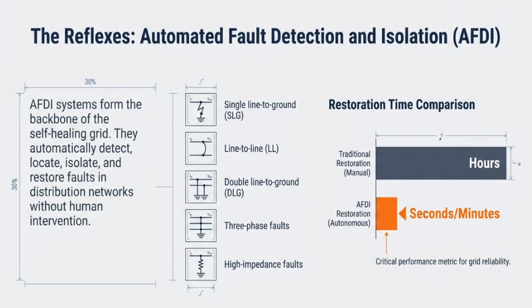So what kind of faults will we be detecting? There are a lot of types of faults happening: single line to ground, called SLG, line to line, double line to ground, three phase, and high impedance fault. Many faults might occur due to natural calamities or human error. It could be anything.